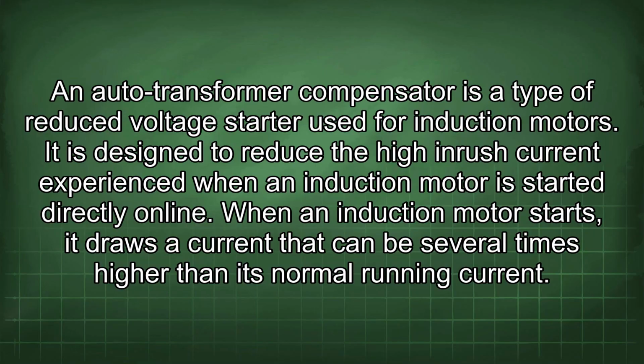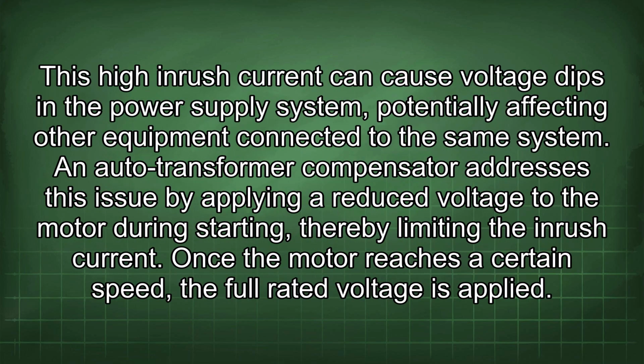An auto-transformer compensator is a type of reduced voltage starter used for induction motors. It is designed to reduce the high inrush current experienced when an induction motor is started directly online. When an induction motor starts, it draws a current that can be several times higher than its normal running current. This high inrush current can cause voltage dips in the power supply system, potentially affecting other equipment connected to the same system. An auto-transformer compensator addresses this issue by applying a reduced voltage to the motor during starting, thereby limiting the inrush current. Once the motor reaches a certain speed, the full rated voltage is applied.